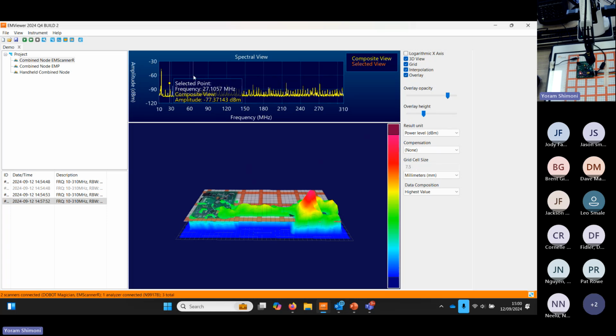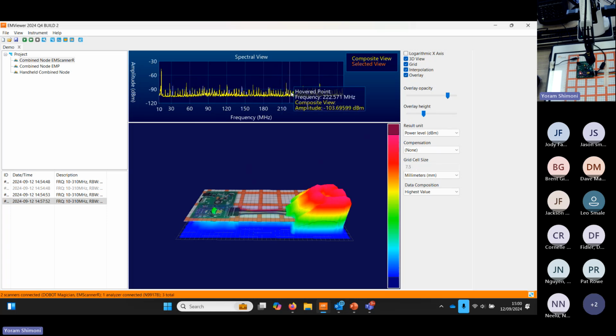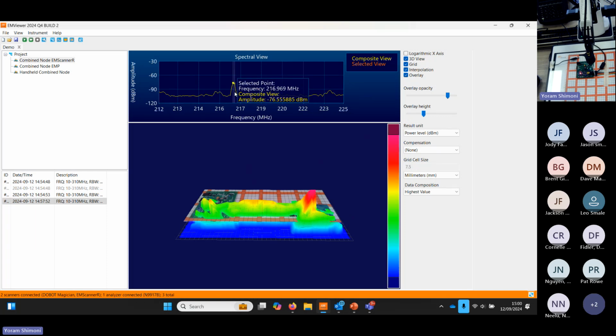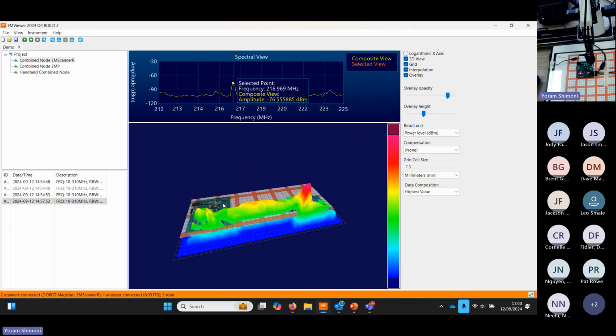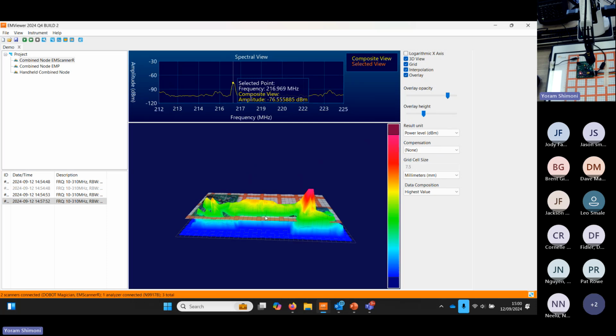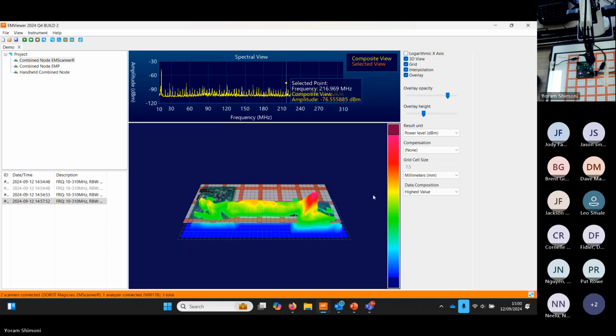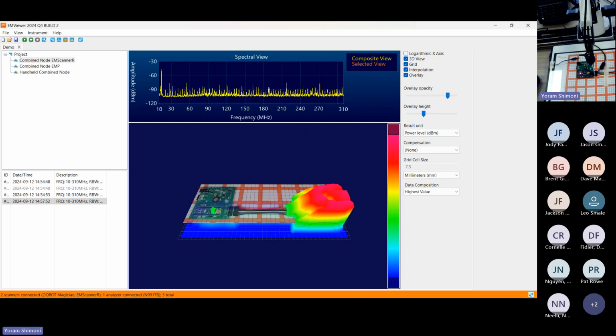Next thing is the sources, the harmonics. So obviously we can see many harmonics here. This one is the 27 harmonic, and it caused damage around here as well - higher frequency, and that travels across the cables all the way to the other side. Very visible.